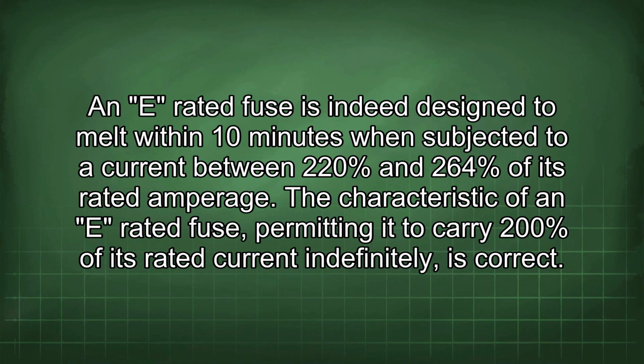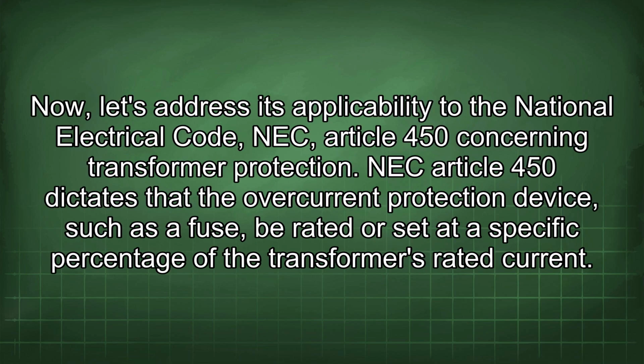An E-rated fuse is indeed designed to melt within 10 minutes when subjected to a current between 220% and 264% of its rated amperage. The characteristic of an E-rated fuse, permitting it to carry 200% of its rated current indefinitely, is correct. Now let's address its applicability to the National Electrical Code, NEC, Article 450 concerning transformer protection.